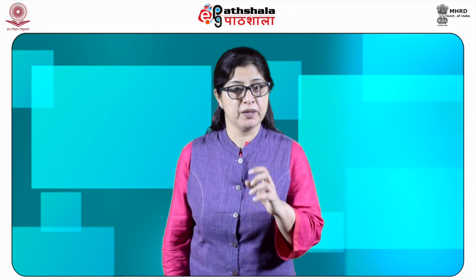Therefore, its removal becomes necessary, which is achieved by passing a solution of calcium or barium ions having the phosphate ions through the sulfonic acid cation exchanger. Softening of hard water. We are aware of the fact that the hardness of water is due to the presence of calcium and magnesium ions and the other divalent ions. These ions may be removed by passing the hard water through the cation exchangers charged with the sodium ions.